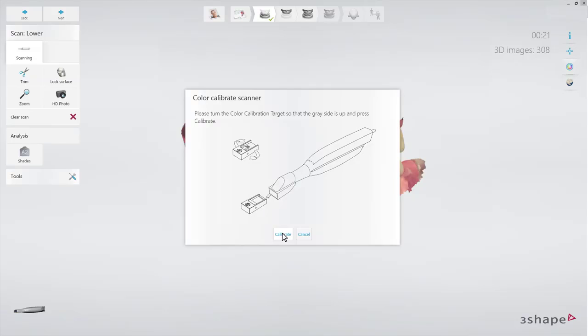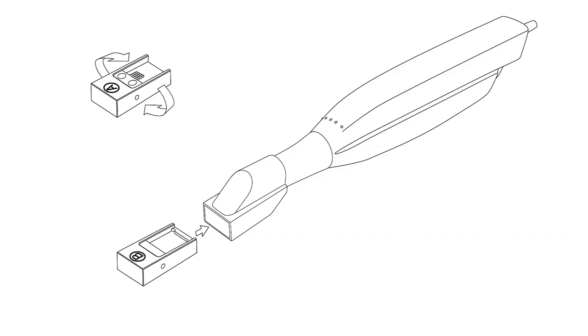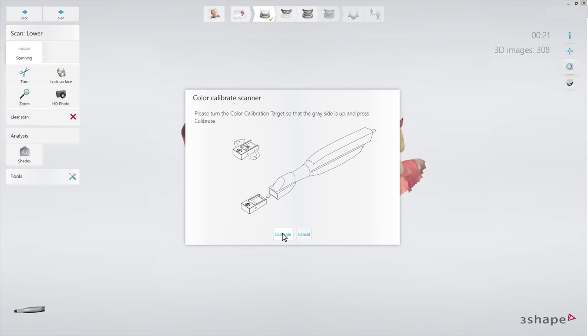The next step is preparing for validation. Detach the color calibration target, turn it over to face upwards on the grey side. While performing this action, make sure that the grey surface is perfectly clean and free of scratches. Upon doing so, reattach it to the color calibration adapter and press Calibrate to start validation. It takes around 30 seconds.